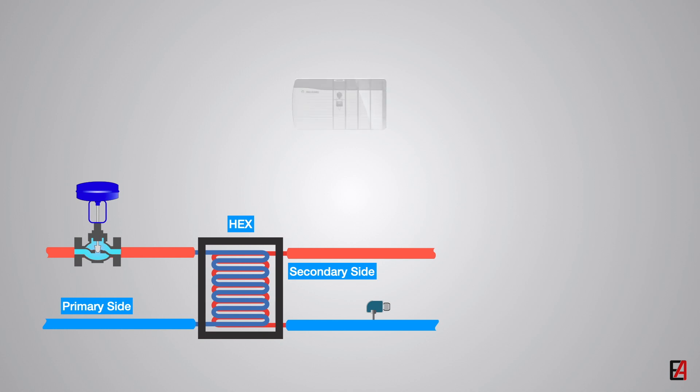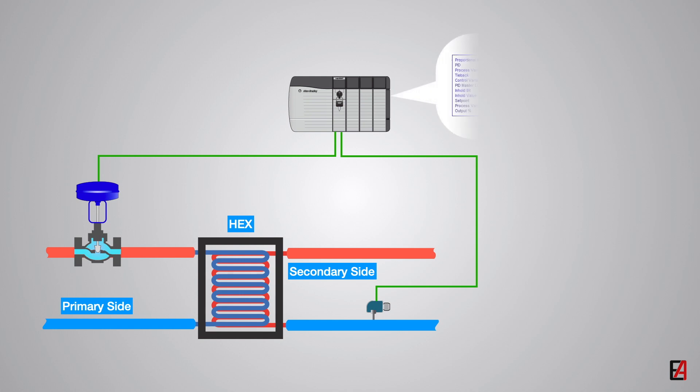In order to maintain the setpoint, the PLC controller will continuously monitor the secondary side temperature and activate the control valve actuator on the primary side to maintain the desired setpoint. The PLC will have a PID controller in order to have optimum control of the heat exchanger secondary side temperature.